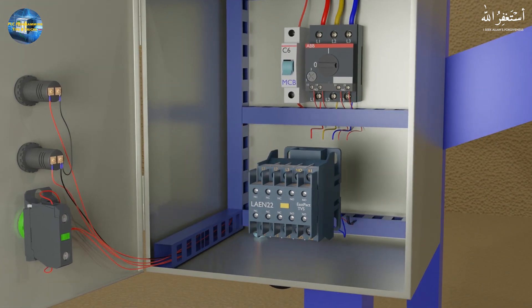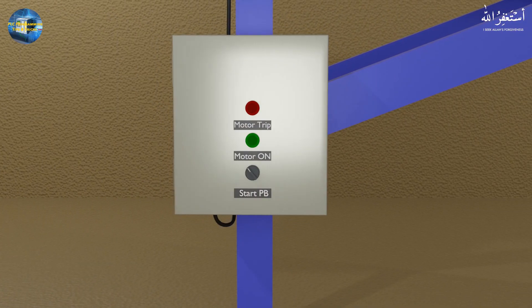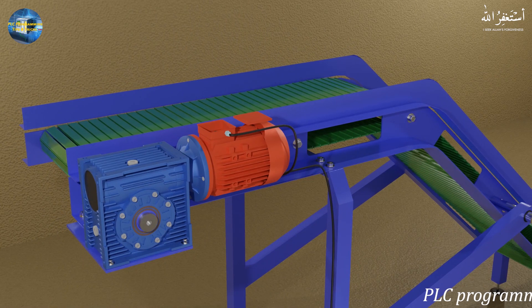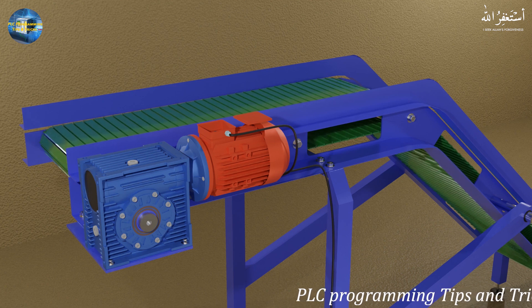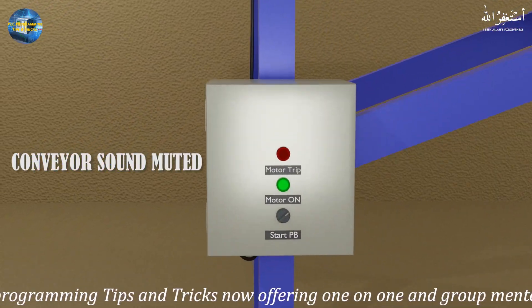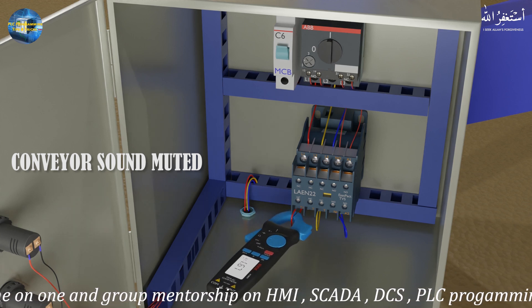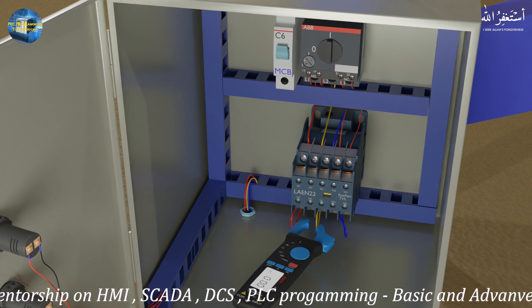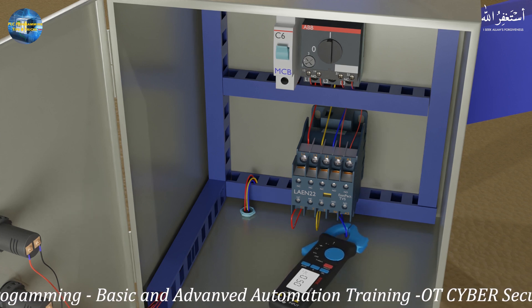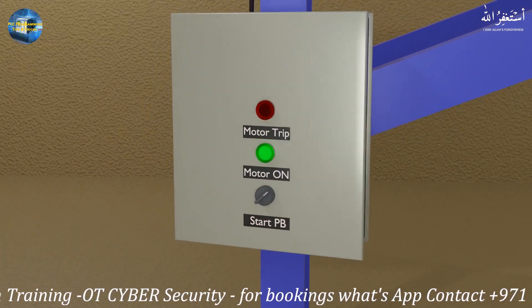We will remove all wiring and replace the contactor. After that, we will put back all the wiring and try to run the motor by turning on the selector switch. As you can see, this time the motor is not tripping or overloading and it is running smoothly. The problem was the faulty contact of the contactor. Now, if we go back to the electrical panel and measure the current across each phase, you can see that the current across each phase is 1.67 amps, very close to the rated current on the motor nameplate. The faulty contactor contact was not allowing current to pass through the yellow phase — we replaced the contactor and the problem has been solved.